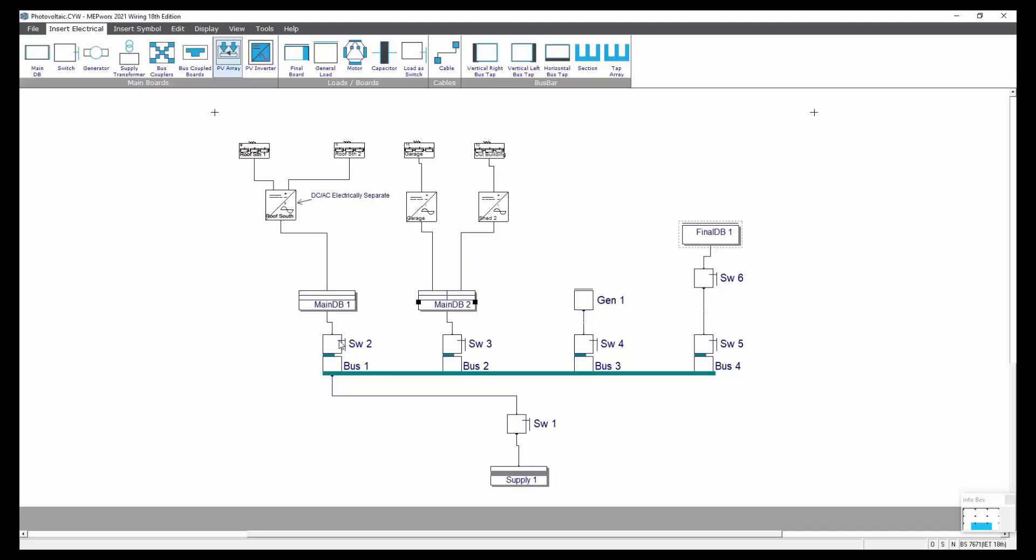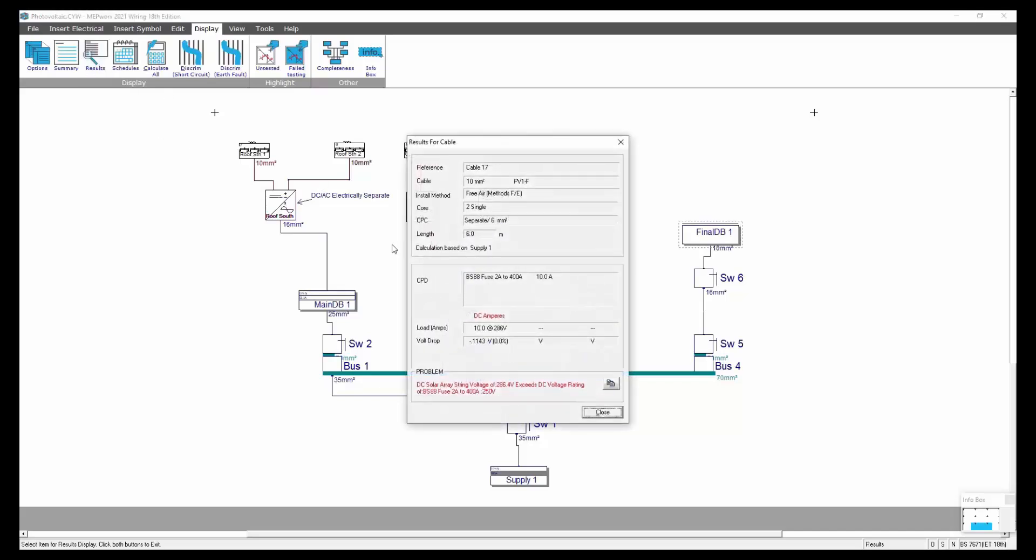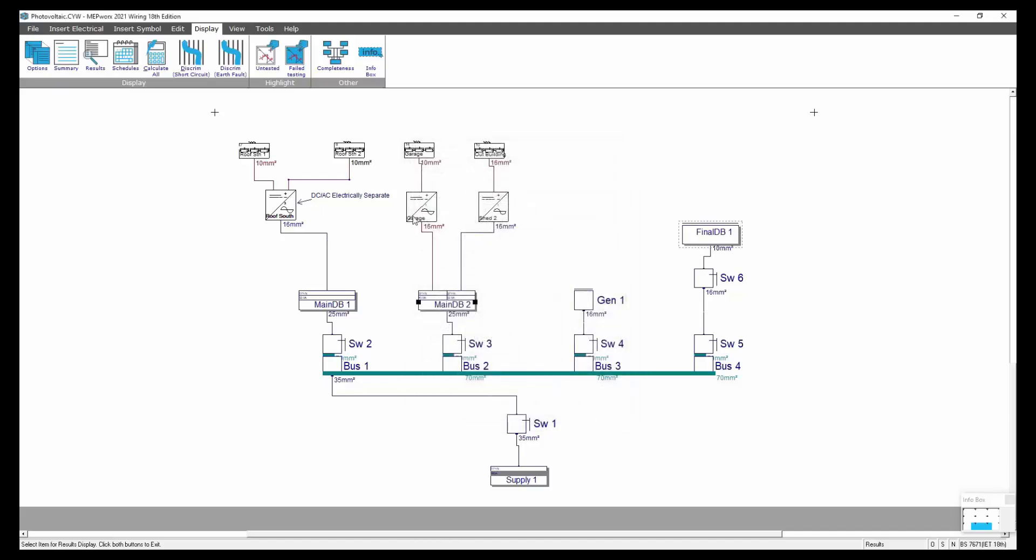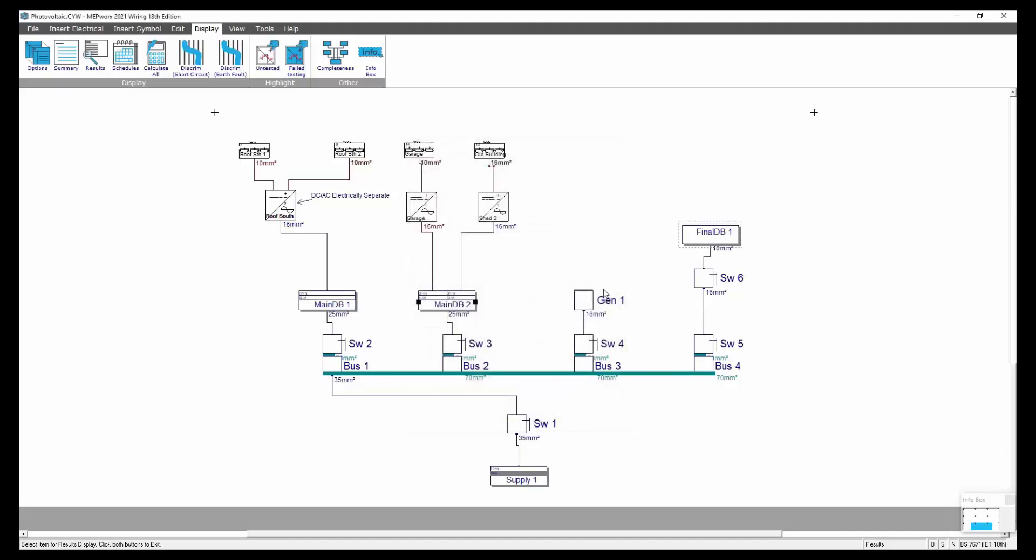The photovoltaics are there so that you can run the calculations. When I then run the display calculator, any problems that are found on the circuits can be highlighted. We can go into results and find out what the problem is. It's saying that the string voltage exceeds the DC voltage rating of the fuse of that particular device. You can see we've got an issue there and it's probably the same with these as well. Any issues that arise are highlighted. So that's a quick overview of the photovoltaics and how you'd set them up.